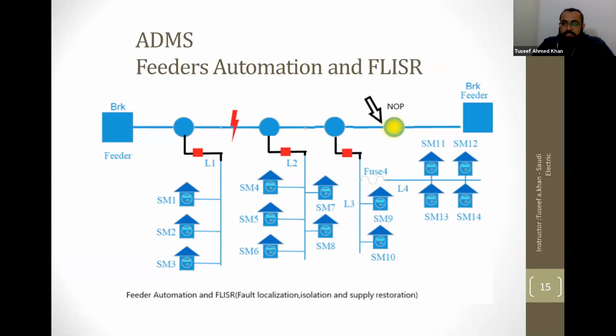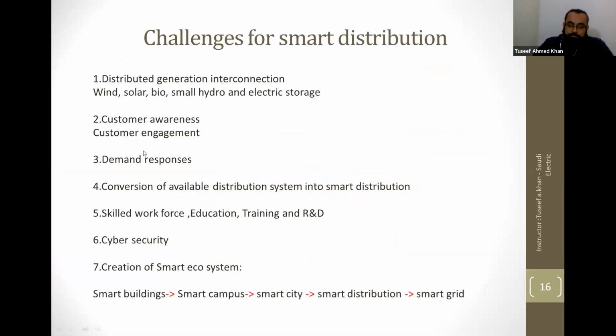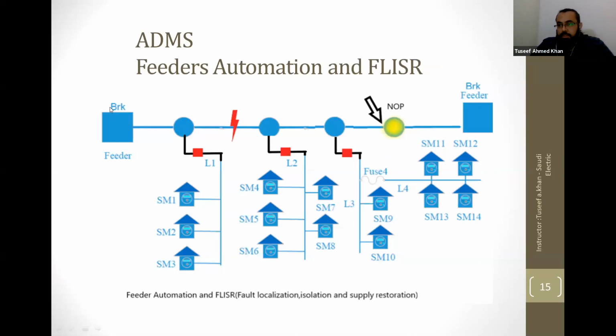Another main part of smart distribution using ADMS software is feeder automation. It starts from the breaker at your primary stations, where you can put fault recorders to record short circuit current. These fault recorders and smart automation at the primary station are part of the smart grid, meaning your smart distribution is now connected with the smart grid system.